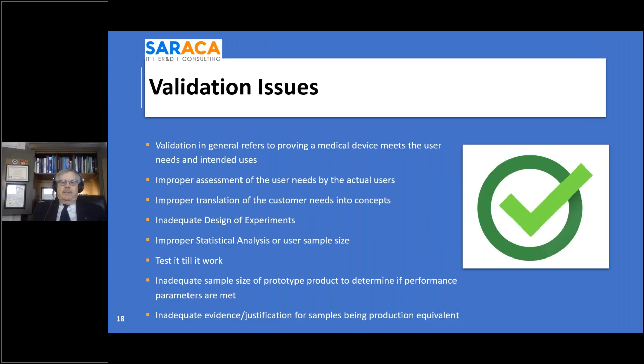And that results in inadequate evidence or justification for the samples being used as production equivalent. Additional validation issues that arise: inadequate risk assessment, the failure to take interaction between variables into consideration, failure in adequate test method validation. What that means is you just can't write a test that you think will validate the essential performance or validate the use of a device in your production methods. You have to make sure that your test method is validated too. You may have shipping testing that's inadequate. Some people just put it on a plane, ship it to someplace and bring it back by truck.